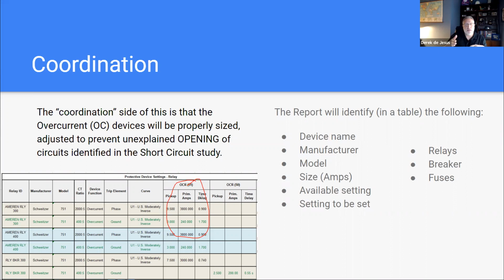And then your short time and instantaneous are a function of that long time current. Your ground fault, if it's LSIG, will be based on the frame rating of that breaker, and it also has its own time band. So when you're validating your trip units and your breaker frame ratings, you want to validate that the bands and the settings available are actually what's on that trip unit or that sensor.